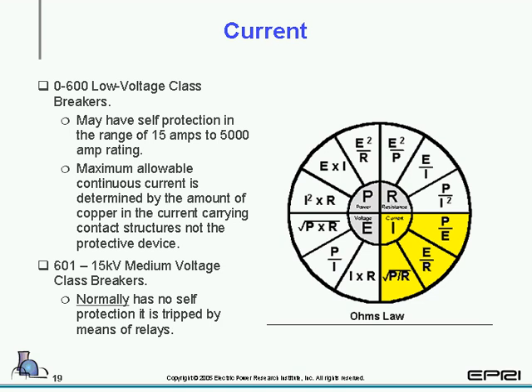The next major one we're going to look at is current. Again, it says 0 to 600 volts, low voltage class breakers. So we're looking at the voltage, and now we're adding the current into that. They may have self-protection in the range of 15 amps to 5,000 amps. And the maximum allowable continuous current is determined by the amount of copper in the current carrying contact structures, not the protective device. You also see that in the medium voltage class below. Normally it has no self-protection. It is tripped by means of relaying. But it is very important to keep in mind that just because the current rating of the breaker is set at whatever value it's at, the protection could be set at a lower value.